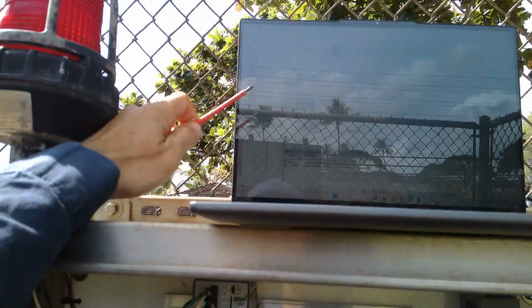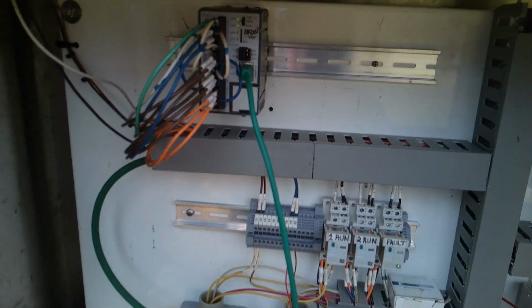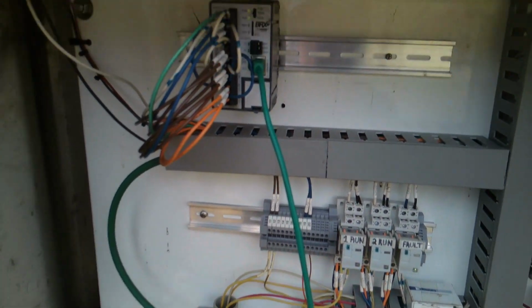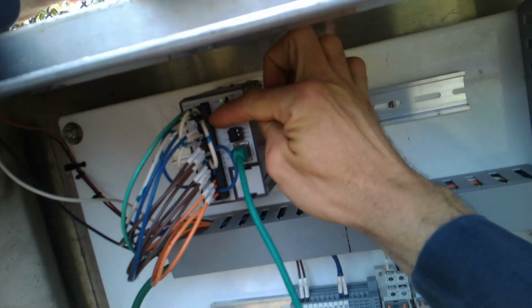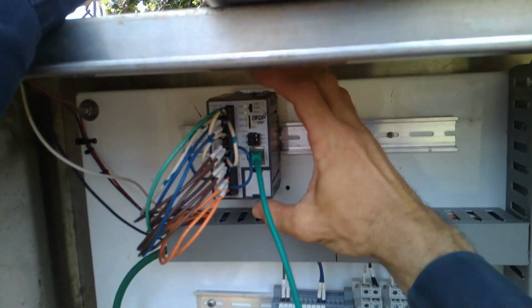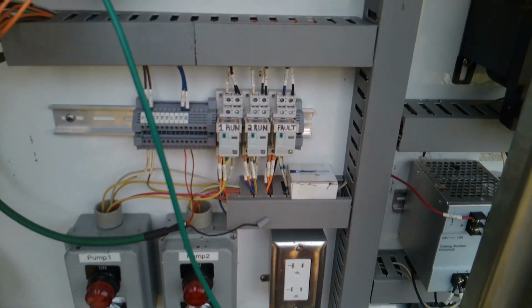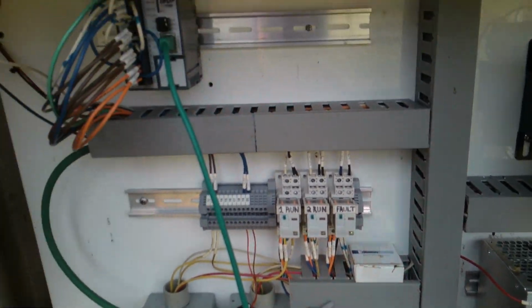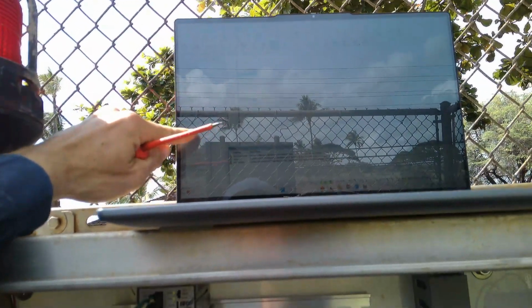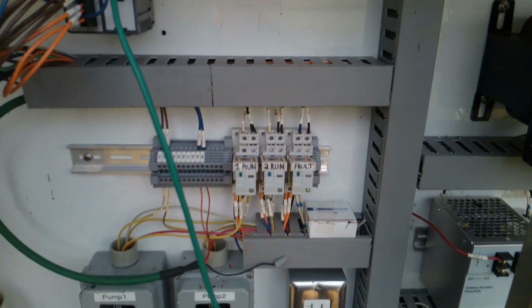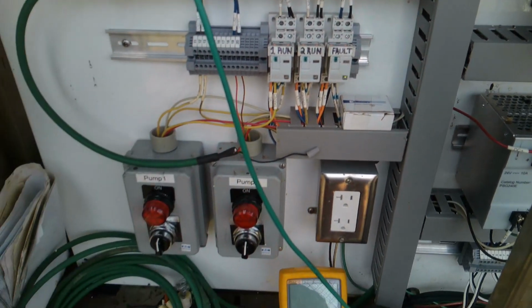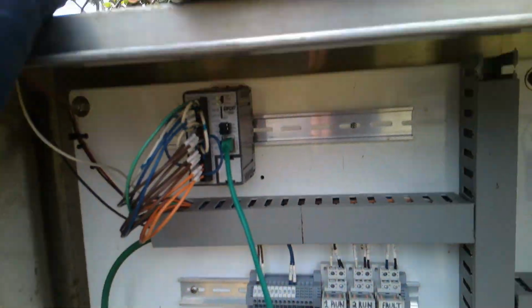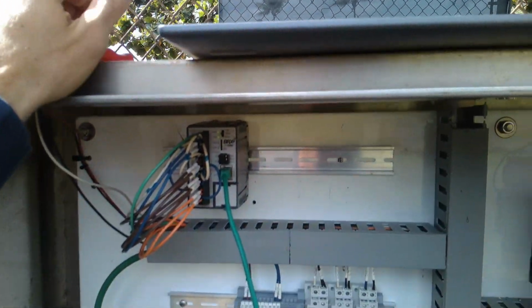verify if this bounciness is strictly because of the field device, or is it because of the actual analog input here in the computer that's receiving the signal? So what I'll do is get a little jumper wire and generate a signal with this guy. We'll look at it here, and if it doesn't bounce here and everything sits happy at like 5% where it was when we connected, then they need a new transducer and we can get the heck out of here.